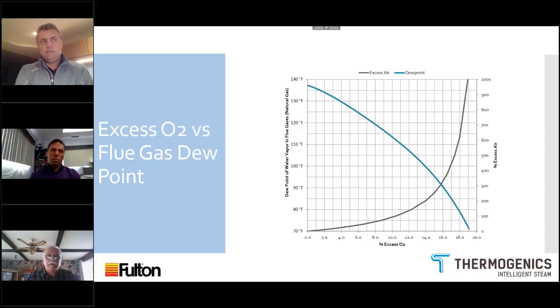This is my personal opinion, but where I find you get a transition between economics and performance is probably around 12 million BTUs and up. It used to be higher than that, closer to 15 million BTUs. The rationale is that the O2 in situ cells that come on these sensors are typically very expensive. They require calibration to operate properly, and they require certain maintenance visits to make sure they're tuned properly. So if you offset the cost of those versus the performance you're looking to achieve, it's around that sweet spot now. I would say around 12 to 15 million BTUs is where these more cost-effective, less maintenance-intensive cells are now providing the payback versus the implementation cost.